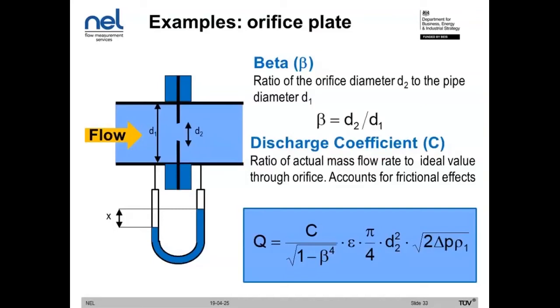The orifice plate is used for flow measurement, and we have a governing equation at the bottom right-hand side of the screen. So we know that flow rate depends on the discharge coefficient, the beta ratio, the expansibility coefficient, the diameters of the pipe and the orifice plate, which gives you the beta ratio, as well as the differential pressure and the density determination. So there's various different components in the calculation, and straight away you can imagine how each of those has its own source of uncertainty. So each of those parameters represents an input into the overall flow measurement uncertainty.